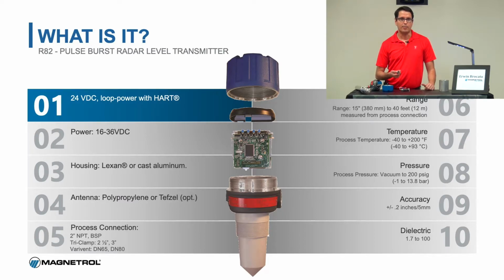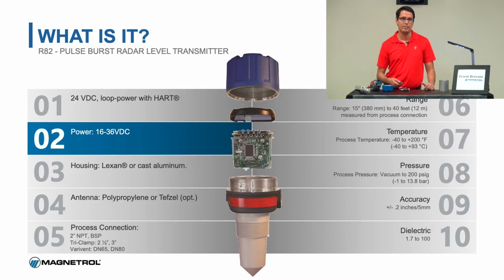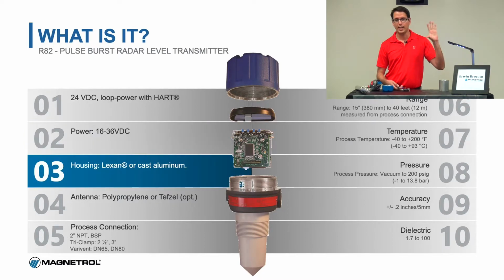The different components of the device: a 24 volt loop-powered device, obviously going back to the PLC. Here's your voltage. There is always a minimum voltage on these devices, otherwise they go to fault. Lexan: whenever you get the Lexan compartment for this device, it's not going to be an explosion-proof device, obviously, because it's plastic, but it can be for a general purpose area or for an intrinsically safe area if you wire it up with the barrier.